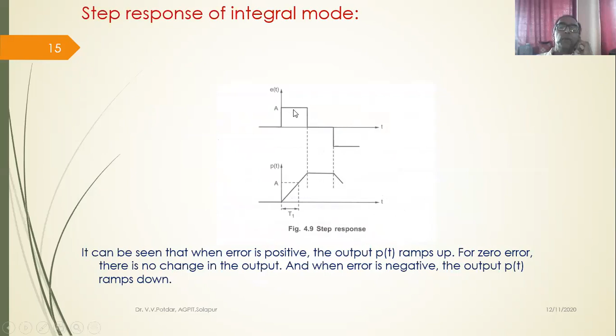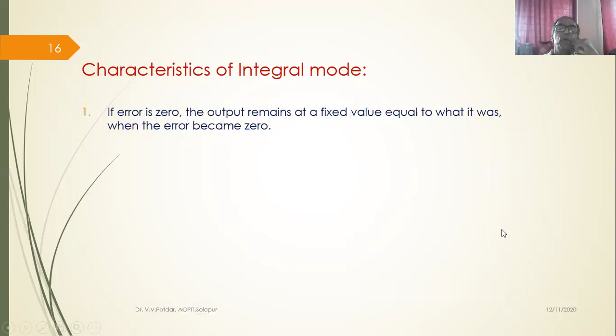Characteristic of integral mode: if error is zero, the output remains at a fixed value equal to what it was when the error became zero. If the error is not zero, then the output begins to increase or decrease at a rate of Ki% per second for every positive or negative 1% of error. So these are the few characteristics. The inverse of Ki is called integral time Ti. So integral time Ti is equal to 1 upon Ki. These are a few of the characteristics of integral control mode.